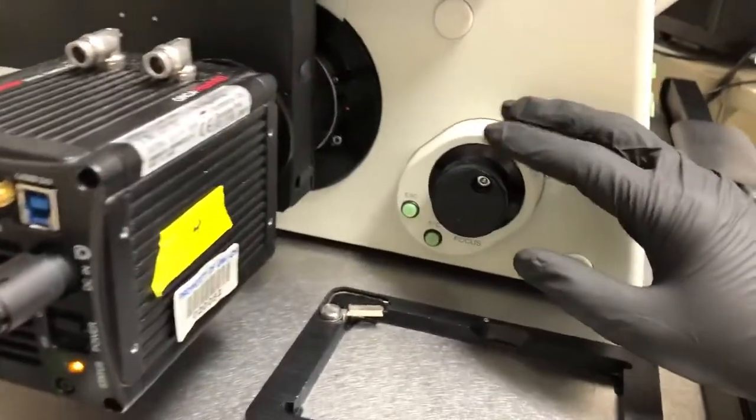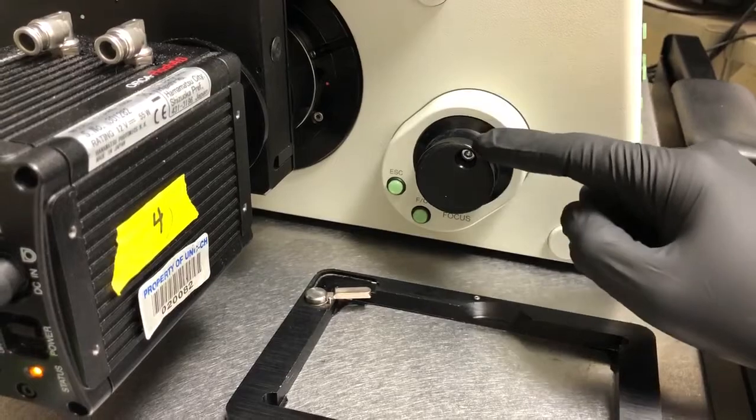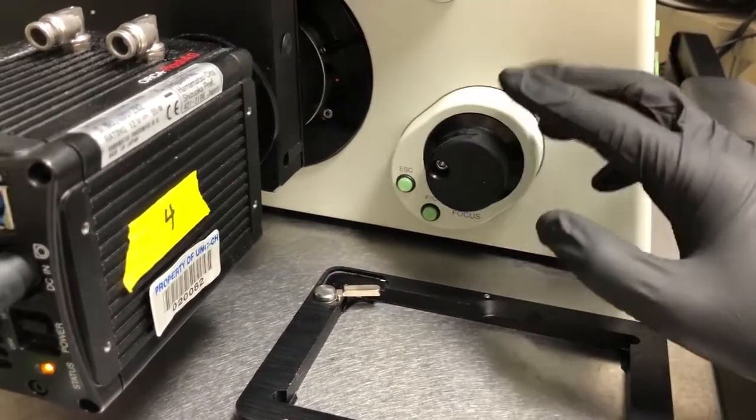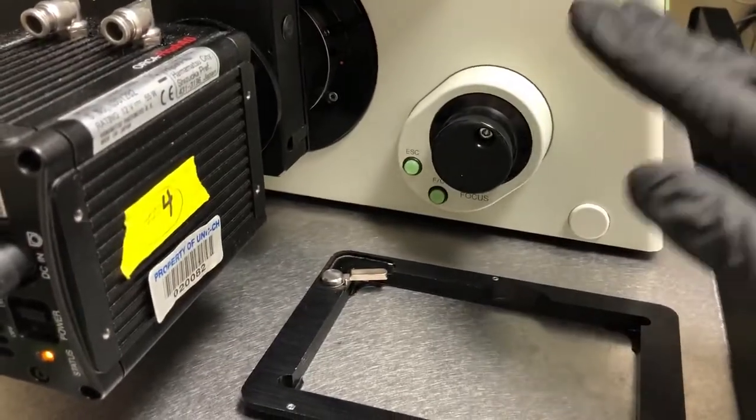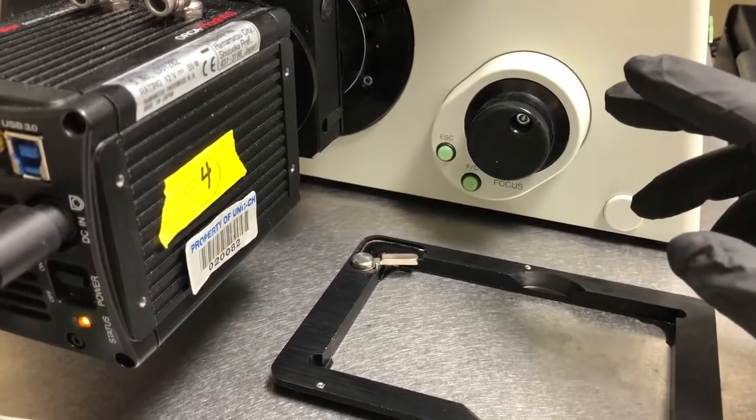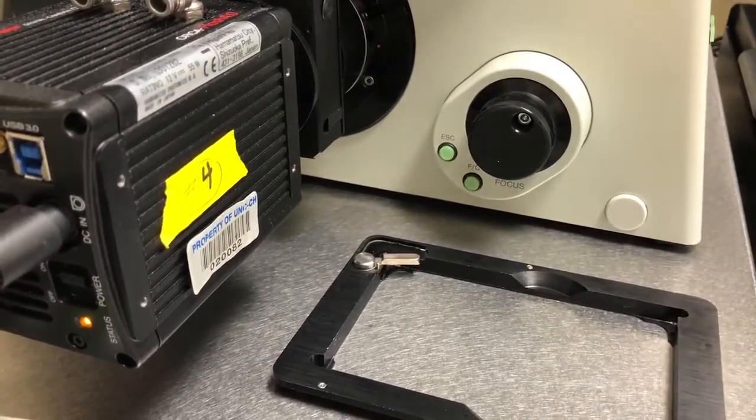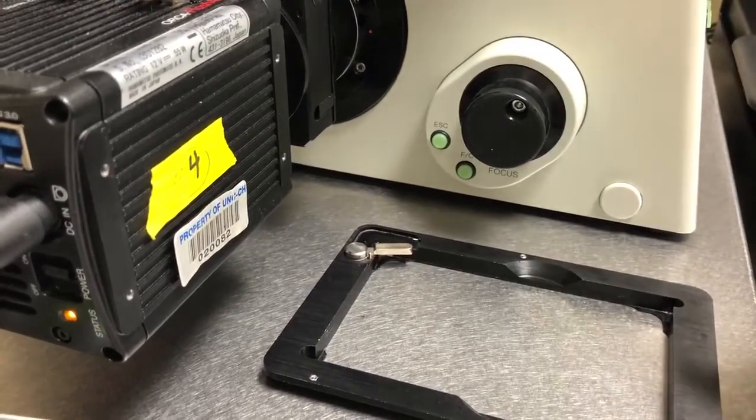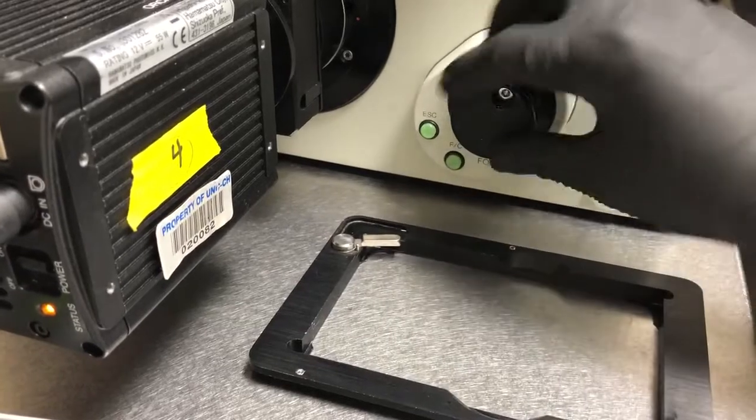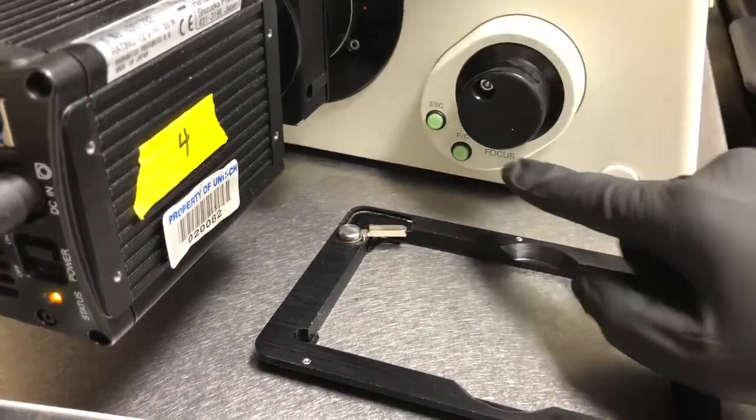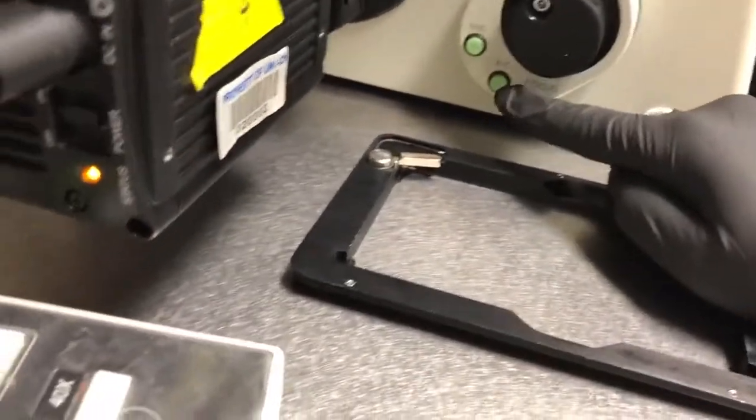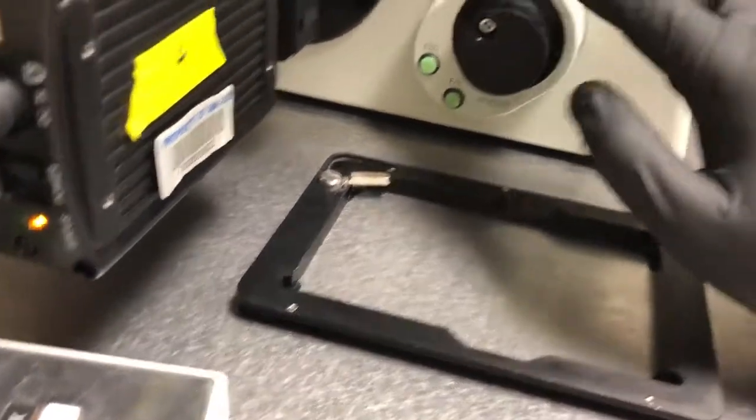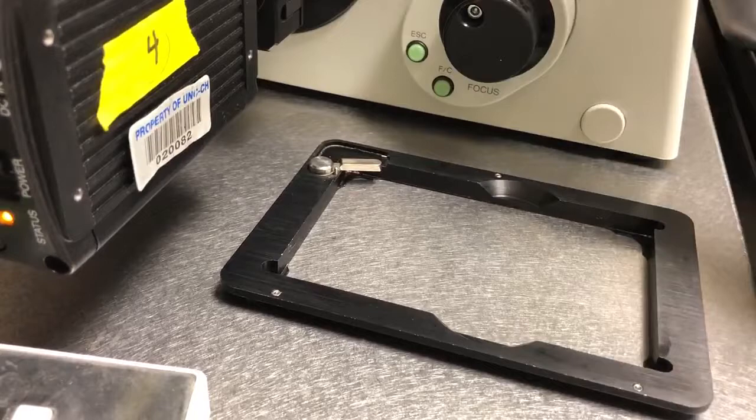Next step is to lower the objectives by pressing the escape key on the microscope. So this focus knob moves the sample either up or down. If you move it away from you, excuse me, not the sample, the objective. So if you move this knob away from you, the objective moves down. If you move it towards you, it moves up. This, keep in mind, is exactly flipped from the Zeiss Confocals. If you're familiar with those, you'll have to flip how you do things to go in the direction you want. In any case, so this moves the objective up and down. There aren't two knobs like on some other microscopes. There's just one. And you can toggle between fine and coarse by pressing this button here. It always starts on fine. So if you press it now, because we just started the system, you go to the coarse.